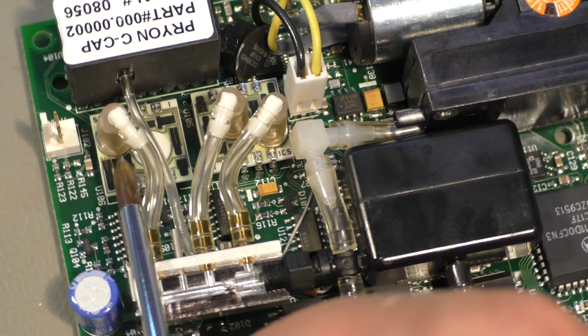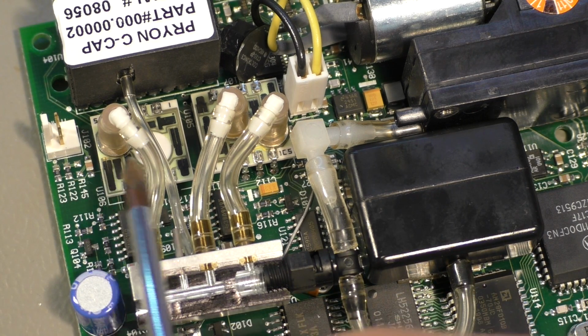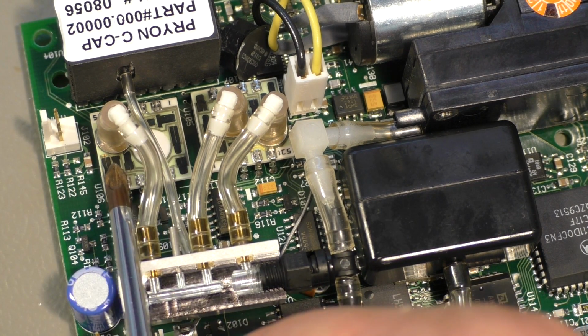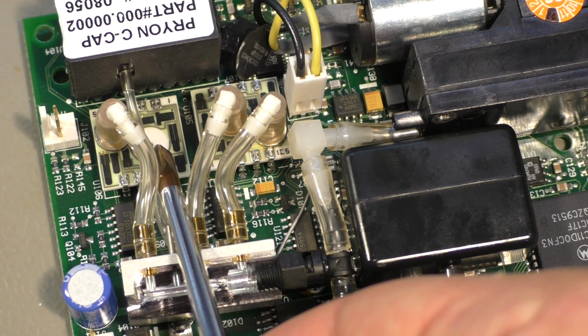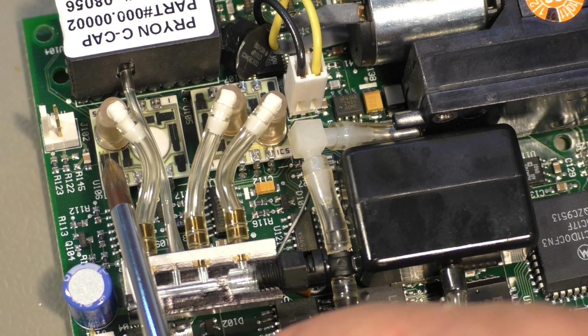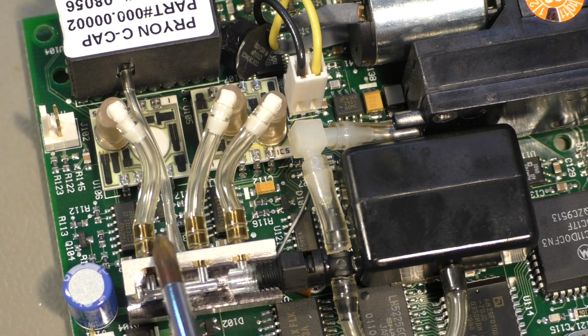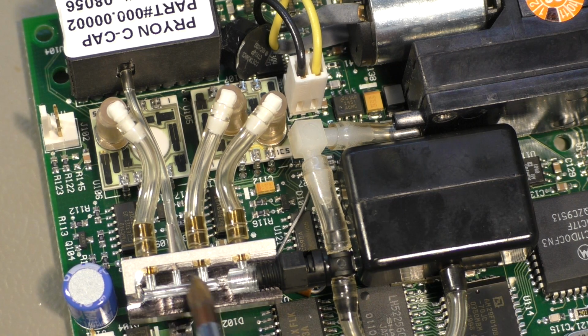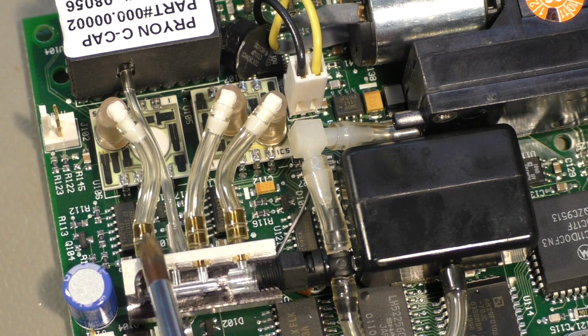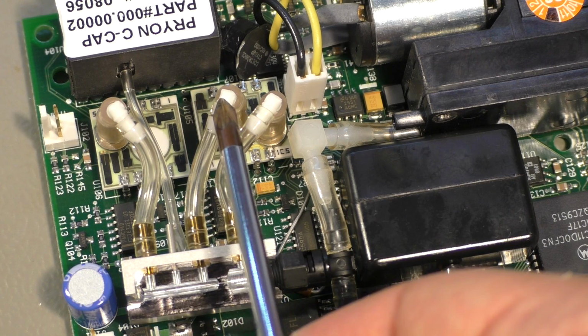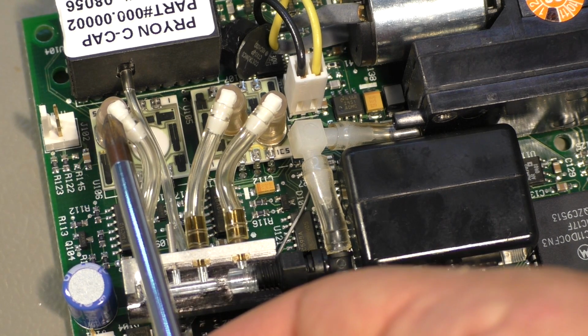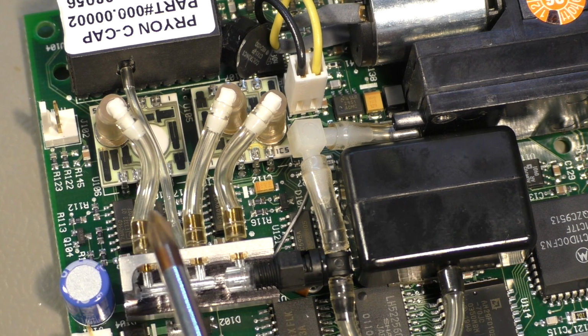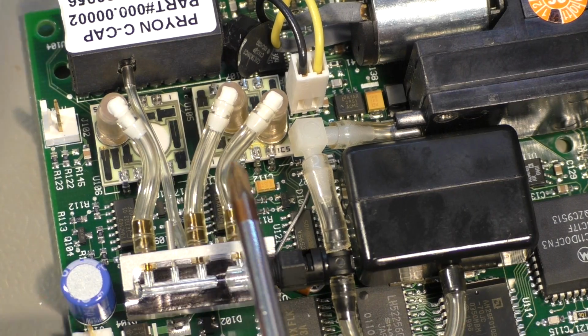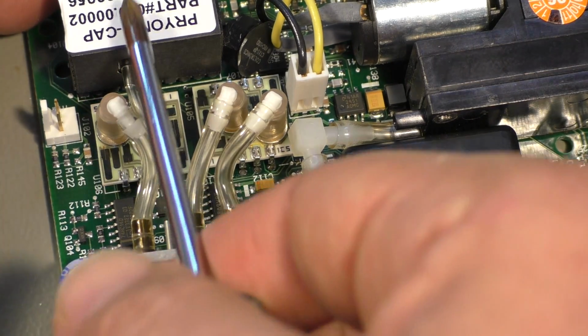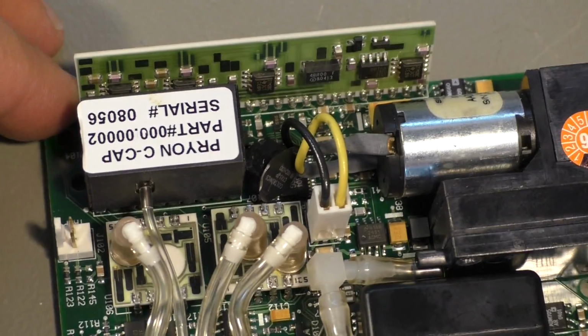Then we have another pressure sensor here. It seems because it only has 1 port, that's an absolute pressure sensor. It is just connected with the other 2 ports here. So that pressure sensor and that pressure sensor, they should measure the same pressure. And then 1 port goes into that thing here. Sorry, I'm off the picture.